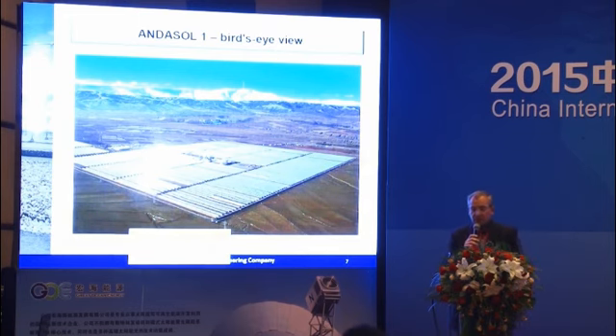It means it's freezing in winter, and in summer it's very hot there. I'd like to draw your attention to the empty spaces in the solar field. When we were developing the project, we considered what to do if the EPC contractor didn't fulfill its contractual obligation and needed to add more power from the sun. So we designed spare loops, empty places, because it's not possible to extend the solar field due to the hydromechanical calculation of the piping, so space had to be found somewhere in the field.